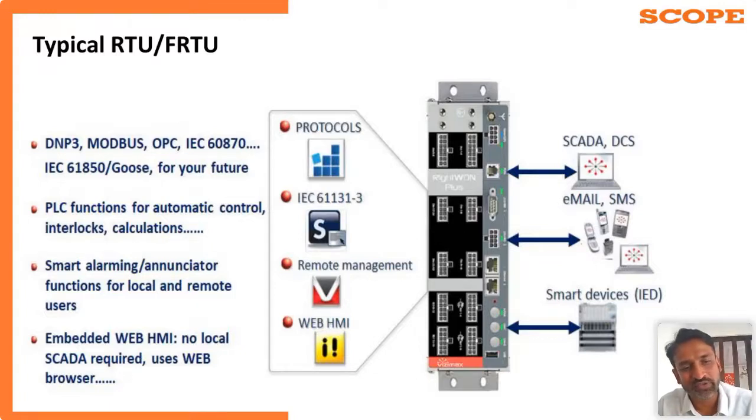Otherwise, if you do not have this web HMI built in, all the data connected at the RTU will be sent to the SCADA. So at the substation, the person cannot understand what is happening here. If he wants to troubleshoot something, he cannot; for him it is a black box. He cannot do anything on that. So when you are considering purchasing an RTU, you have to look at this web-enabled HMI. This will give you more advantage, more troubleshooting options at the local level.